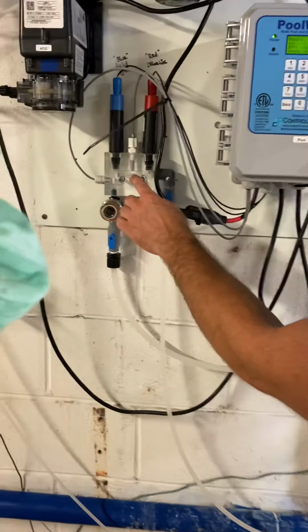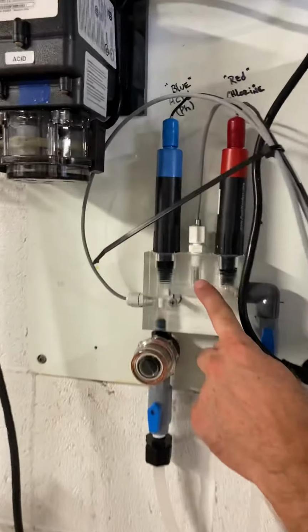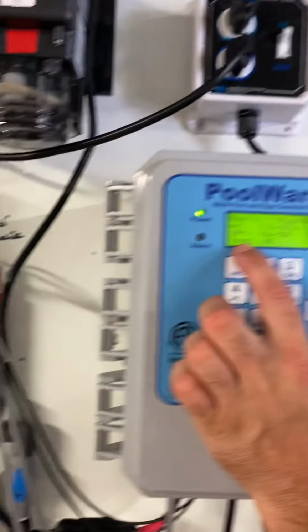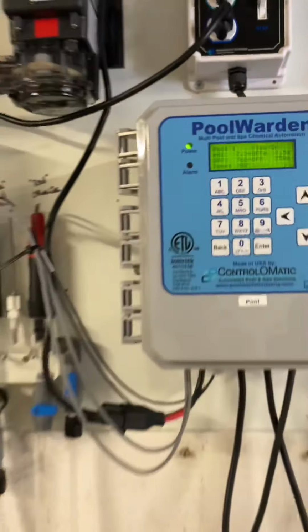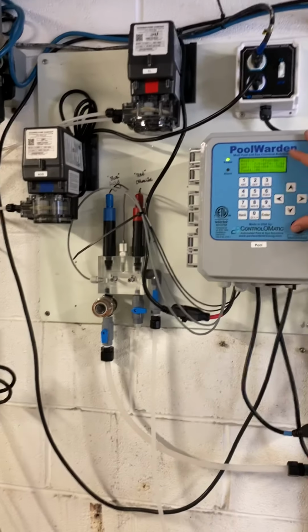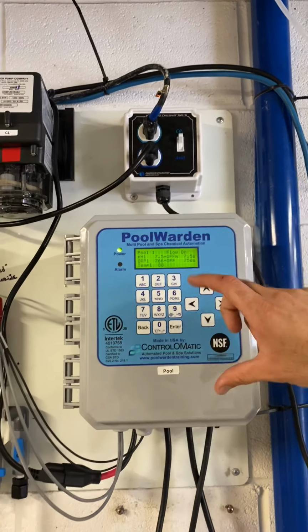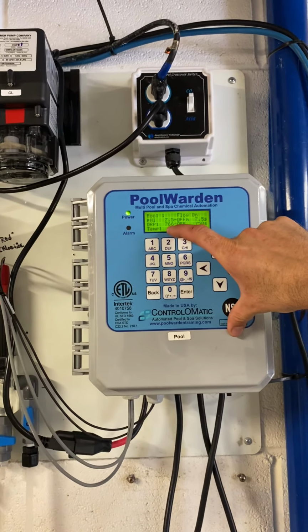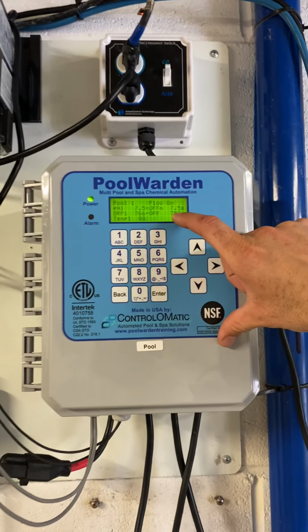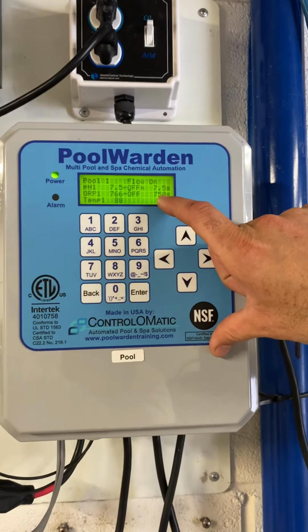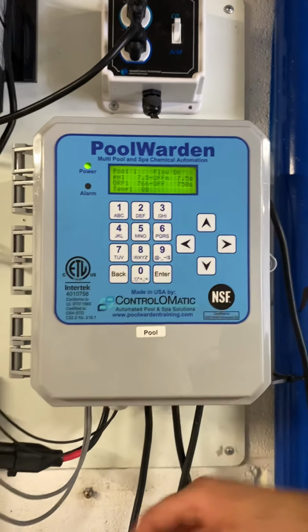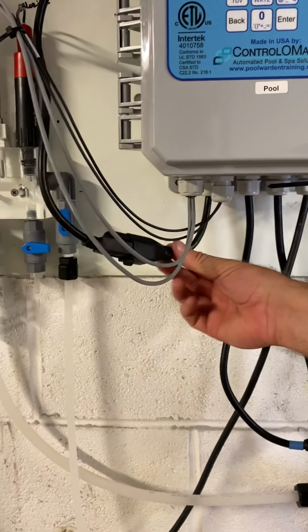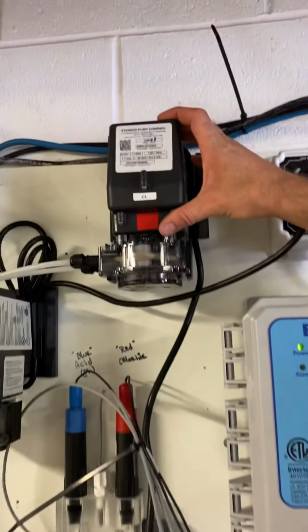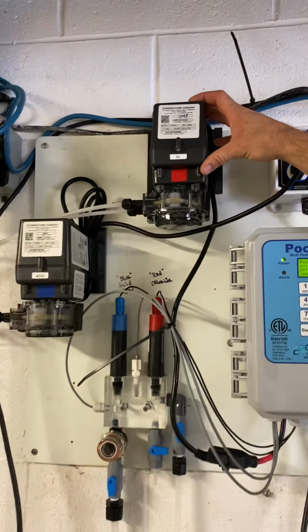This also has a temperature sensor right in here, which is sending the signal up to here, so you can see your temperatures displayed there. Temp 1 is 88 degrees. Okay? So anytime this calls for, we talked about the pH control, anytime this needs chlorine, which is when the ORP reading of 766 drops below our program set point of 750, it's going to call for chlorine, activating the relay, sending power through this pigtail up into your chlorine pump. This is your Stenner chlorine pump.